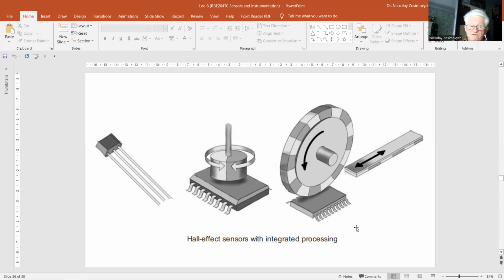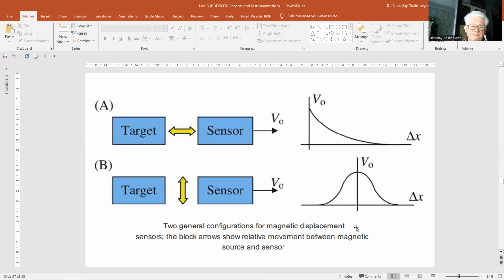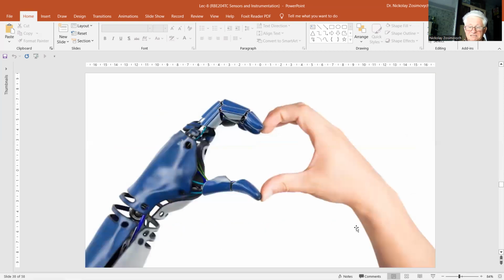A linear proportional Hall effect sensor, as you can see from this slide, in combination with static magnets, exhibits a strong nonlinear behavior as shown in this figure, due to the inhomogeneity of the magnetic field. Therefore, they can be used primarily as switching type or limit type sensors. However, it is well possible to linearize this behavior, especially where space constraints are the most limiting factor. These sensors can still offer a reasonably accurate position reading.